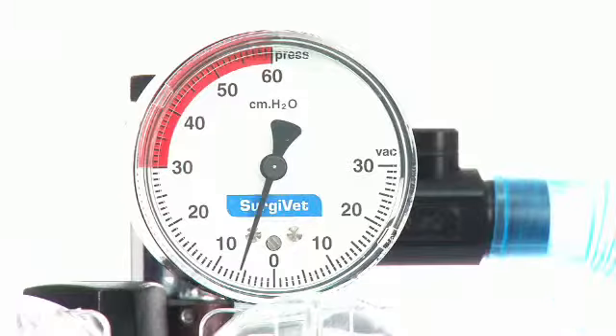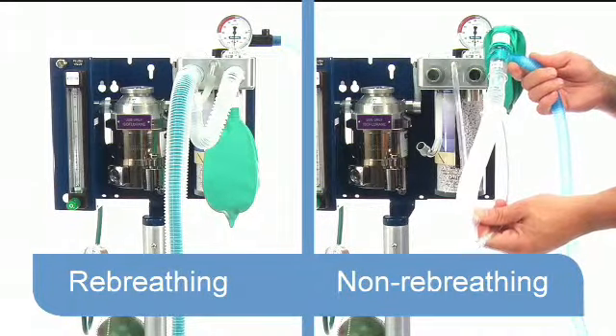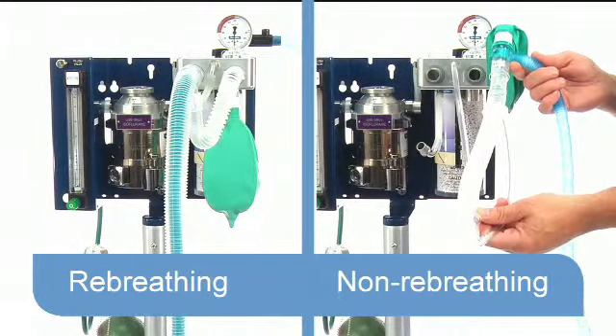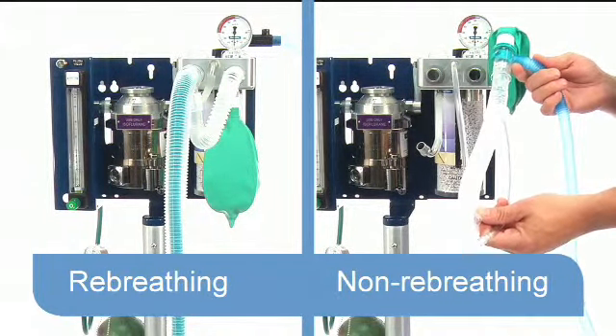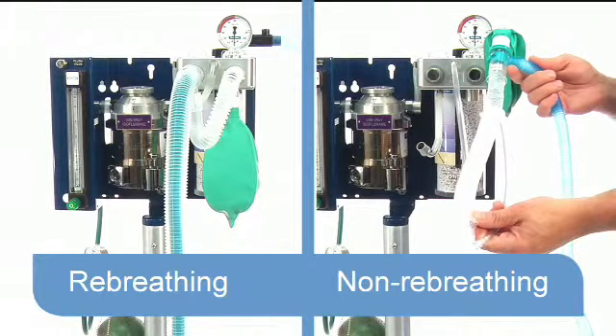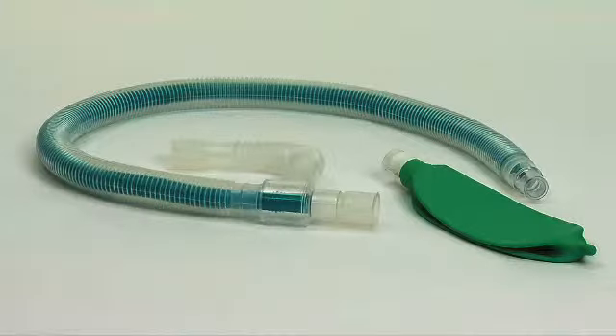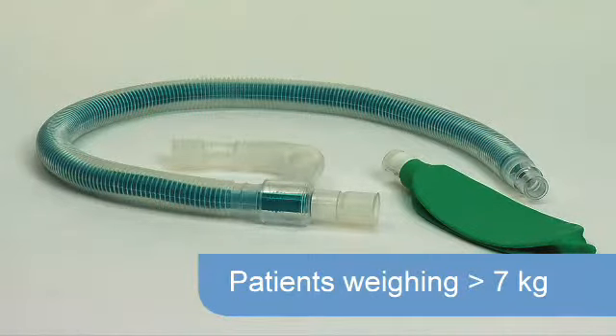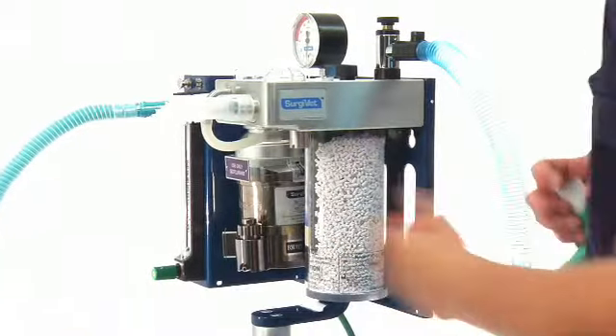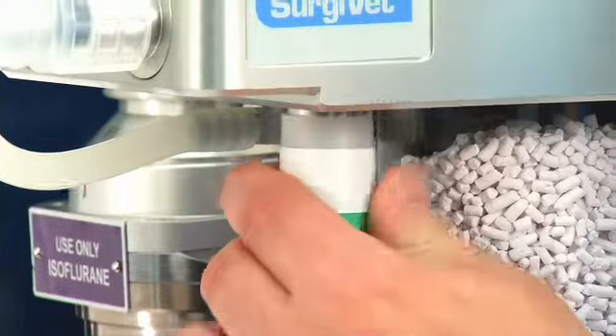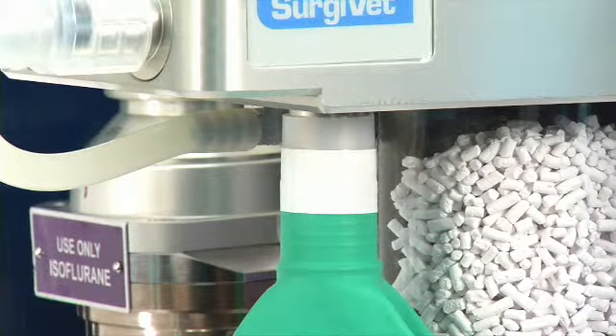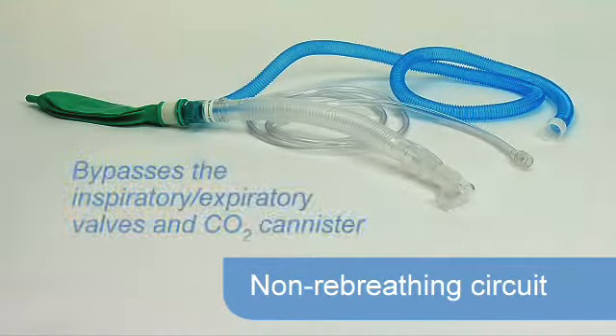Upon release of the button, pressure is released from the system. Two breathing circuits are included with the anesthesia machine, a rebreathing and a non-rebreathing style. The rebreathing circuit features coaxial tubing for patients weighing greater than 7 kilograms. The breathing bag is connected to the bag port located under the exhalation valve. The non-rebreathing circuit bypasses the inspiratory-expiratory valves and CO2 canister.